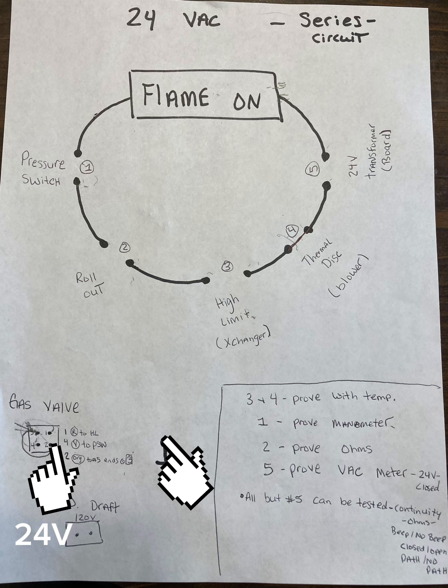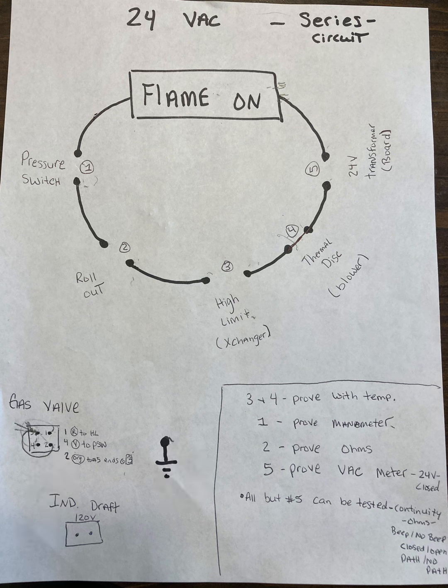Or did the voltage stay and you still lost flame? And you can test all of your safeties real fast right at this particular gas valve, right off the 1 pin. It's going into the high limit switch, so it's right on that control circuit. So you can hopscotch right onto that pin right at the gas valve and watch all the safeties. Man, I lost flame and all of my safeties are closed. So this helps us as a technician not waste a lot of time scratching our head.